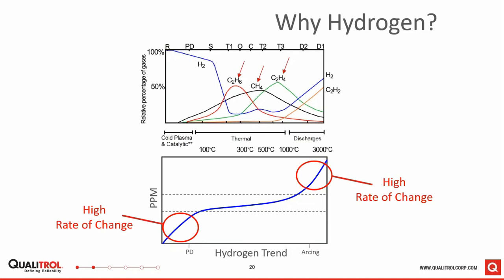As the temperature increases, in the middle range, where the methane, ethane, and ethylene are being created, the amount of hydrogen in the oil on a percentage basis is typically lower than your methane, ethane, and ethylene. It's not that Donald's prior slide was incorrect. In the mid-range we are producing a lot of hydrogen, but that hydrogen is actually being consumed to create the methane, ethane, and ethylene. A lot of times people will say, I look at my DGA report and I've got methane, ethane, and ethylene, but I don't have any hydrogen. Part of that is because the hydrogen is being consumed to create the methane, ethane, and ethylene.